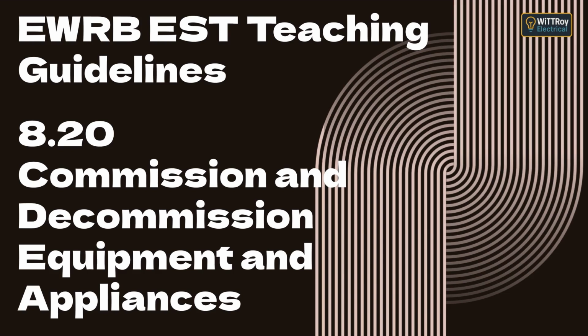Topic D. Consequences of interchanging conductors on a single-phase 230 V motor. Now for Topic D. What happens if conductors are interchanged? Let's go through each possible mistake one by one. 1. Active and neutral reversed. If the active and neutral are swapped, the motor may still run, but the switch and fuse could now be in the neutral conductor instead of the active. This means parts of the circuit remain live even when switched off, creating a serious electric shock hazard during maintenance.